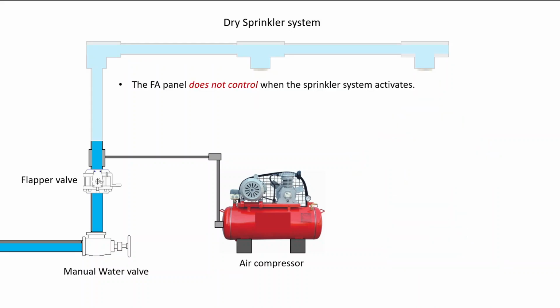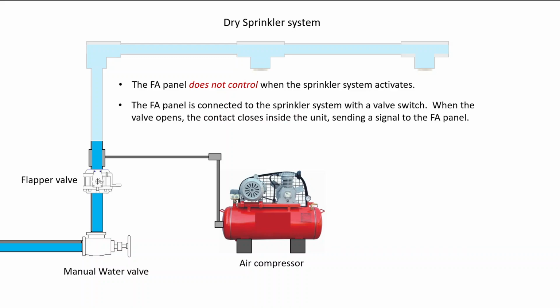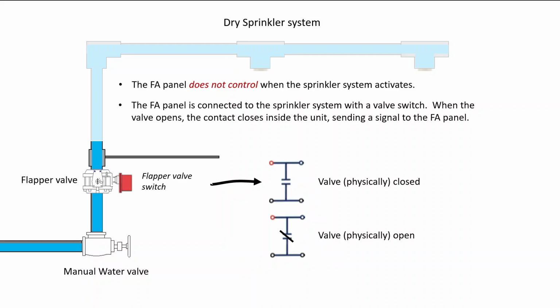Again, it's important to understand that the fire alarm panel does not control when the sprinkler system activates. The fire alarm panel is connected to the sprinkler system with a valve switch. When the valve opens, the contact inside will close, sending a signal to the fire alarm panel. So there we can see the flapper valve switch mounted on the flapper valve, and it all comes as a designed unit for use with fire alarm systems. And we have a contact in there, open, closed, pretty basic.